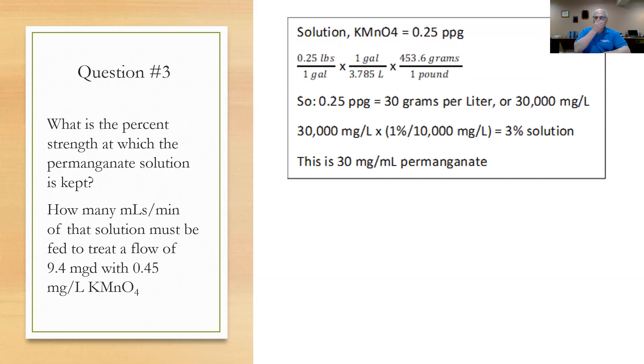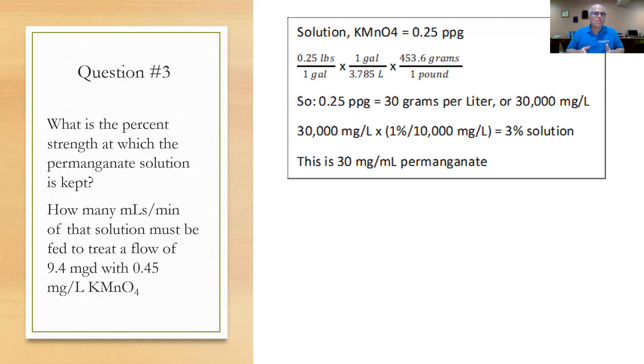From the table, the solution strength is 0.25 pounds per gallon. To convert to percent, multiply 0.25 lb/gal by 3.785 liters per gallon and 453.6 grams per pound, giving 30 grams per liter, or 30,000 mg/L. Since a 10,000 mg/L solution equals one percent, a 30,000 mg/L solution is three percent. A three percent permanganate solution contains 30 milligrams per milliliter, so every milliliter of permanganate added to the water contributes 30 mg of KMnO₄.